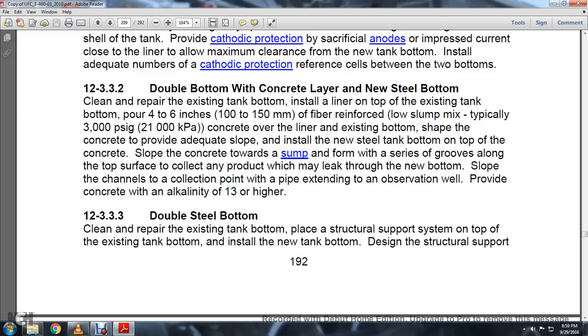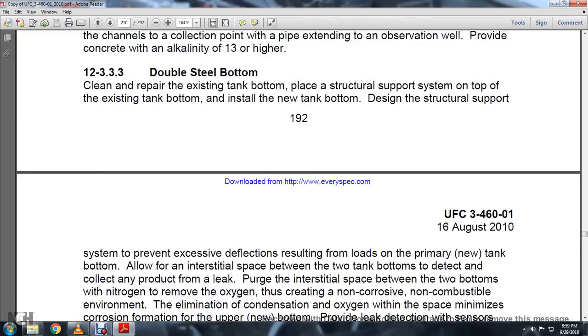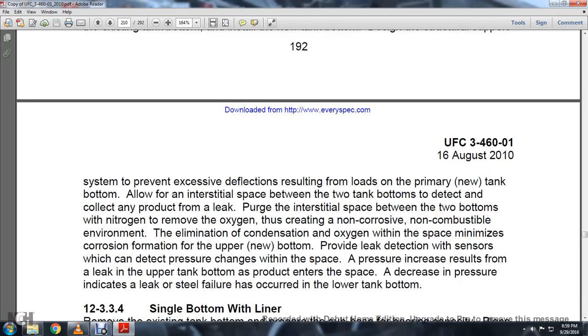Section 12-3-3-3: Double steel bottom. Clean and repair the existing tank bottom, then place a structural support system on top and install the new tank bottom. Design the structural support system to prevent excessive deflection. The interstitial space between the two tank bottoms collects product leaks. Purge the interstitial space between the two bottoms with nitrogen to remove the oxygen, creating a non-corrosive, non-combustible environment and minimizing condensation and corrosion. Provide leak detection sensors that can detect pressure changes in the space — a decrease in pressure indicates a leak or steel failure has occurred in the tank bottom.